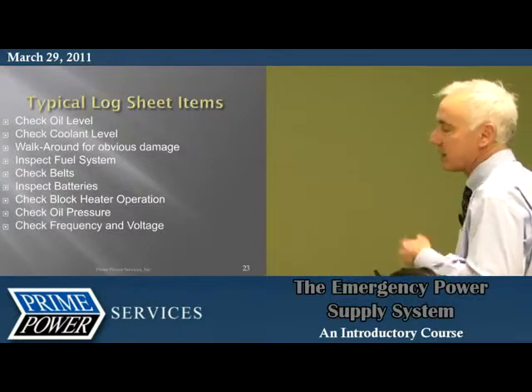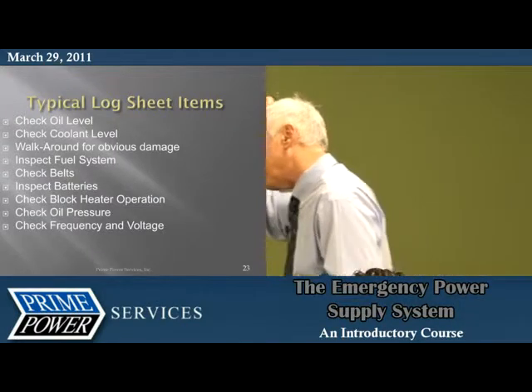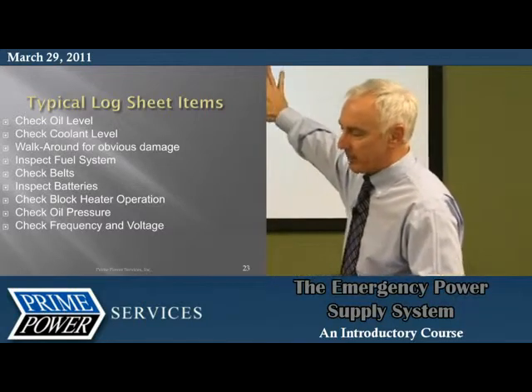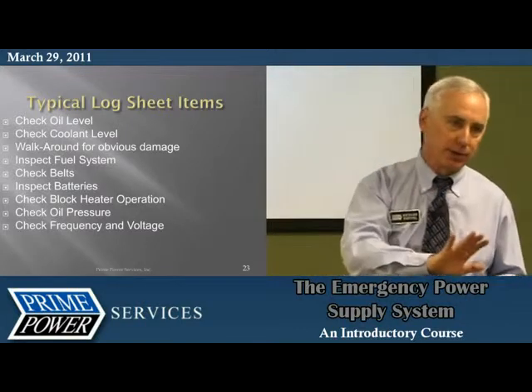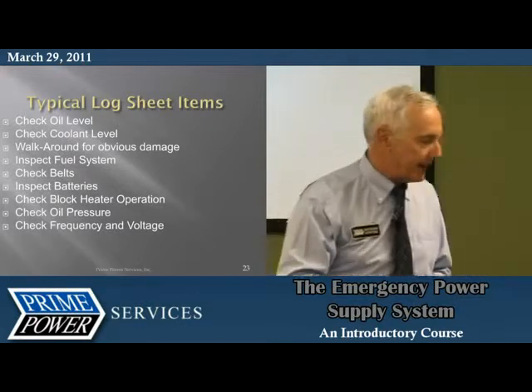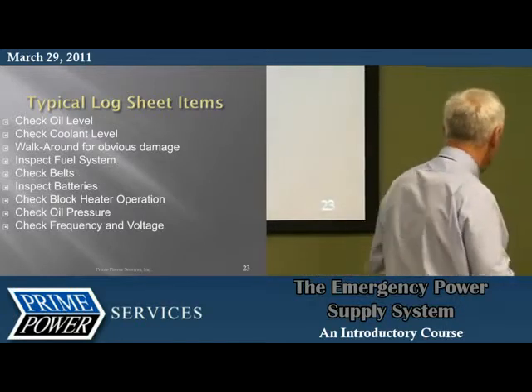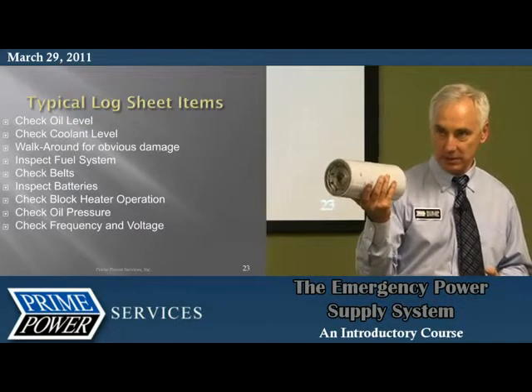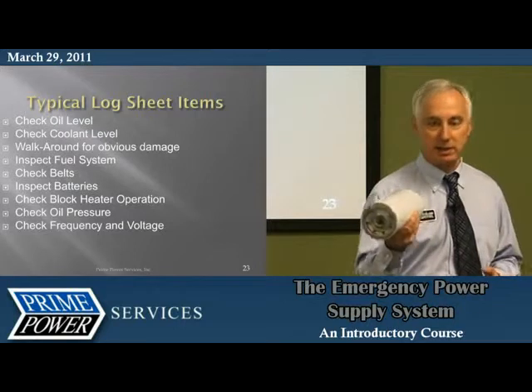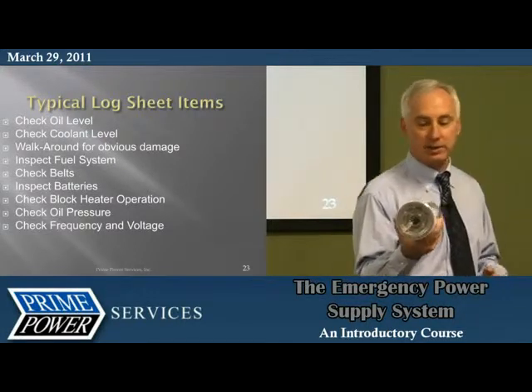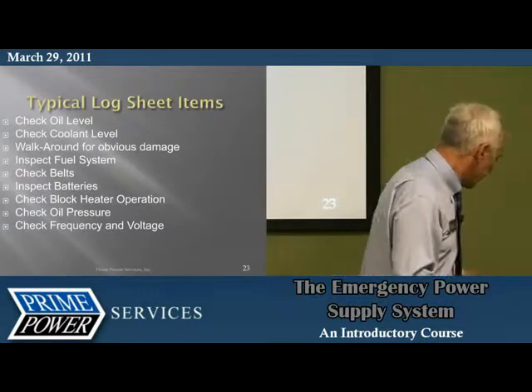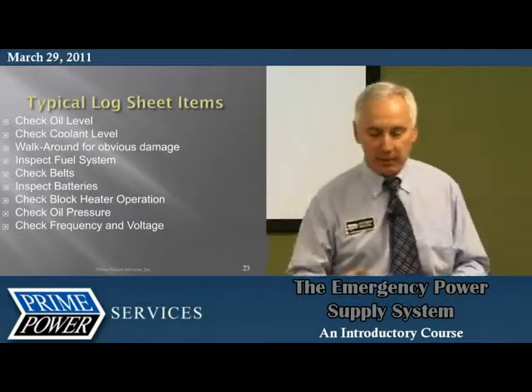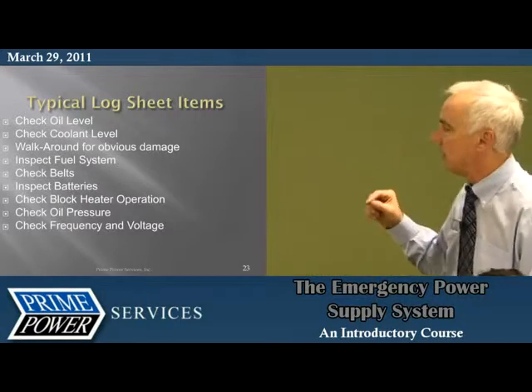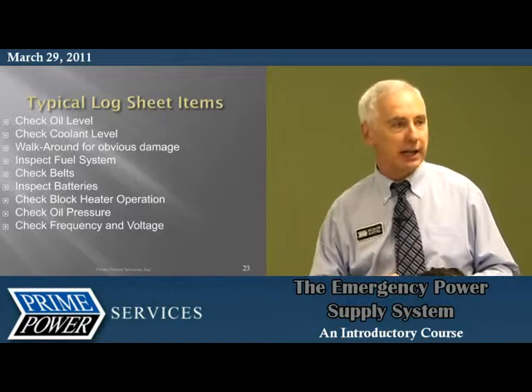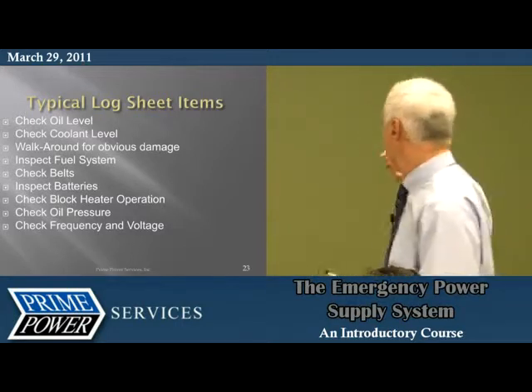Inspect the batteries - we've got some pictures here, we'll talk more about them. Besides spare parts, you guys are supposed to have any special tools related to your equipment on site. That may mean, do you have what it takes to unscrew this filter? If you've got this as a spare part, the implication is you'd be changing it - well, can you? I don't care if it's a big pair of channel locks or a spike you drove through and twisted off, but whatever it takes. And if we're going to actually inspect our batteries, do we have a voltmeter, something to check specific gravity? If we're going to do this correctly, do you have those tools? I'm not expecting some goofy torque wrench, just stuff to do the job you're required to do to make sure this works.